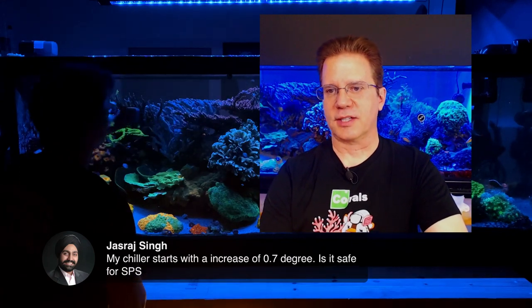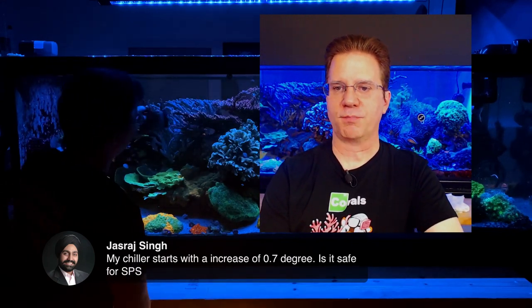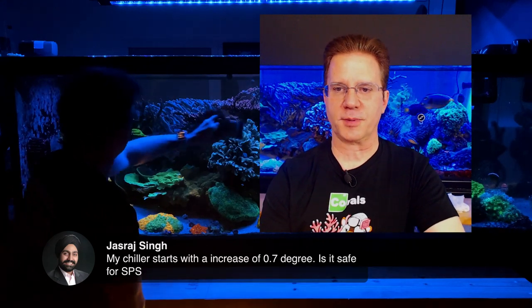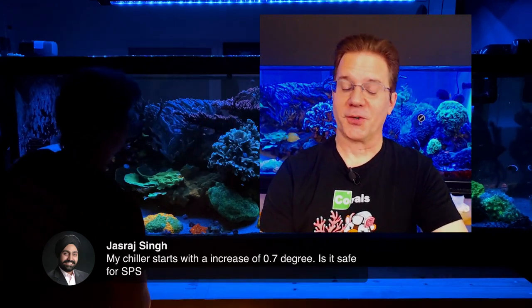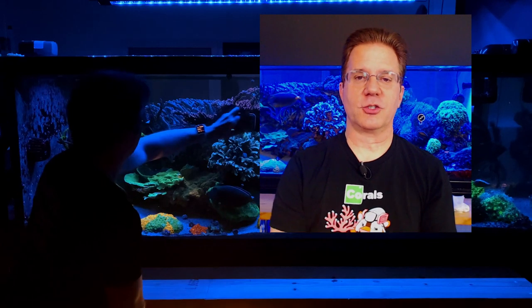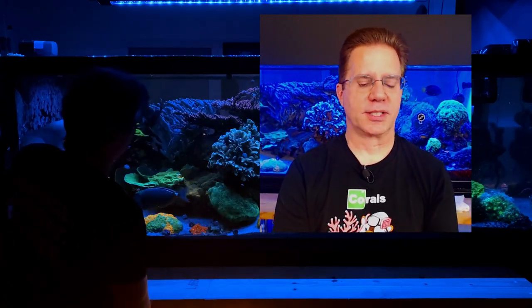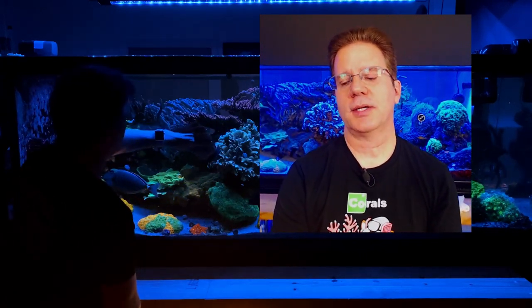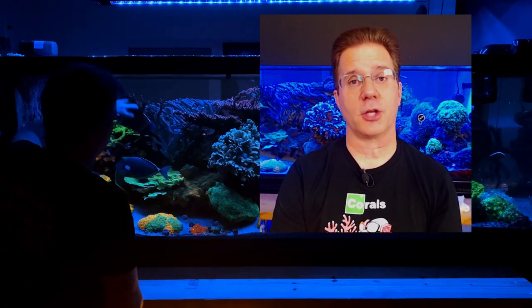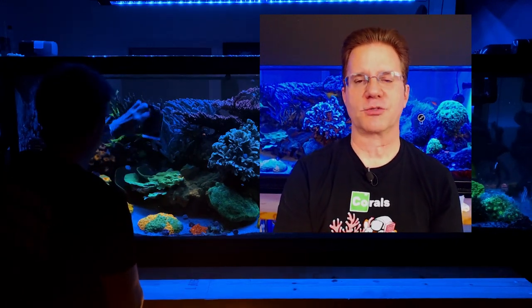Jess Raj says, my chiller starts with an increase of 0.7 degrees - is that safe for SPS? I don't know, I don't know what your area is. You just said when your chiller comes on, but that's a very tight margin and might be too tight. It might make your chiller cycle on and off a lot. It might be better to have like a 1 degree swing, 1.5 degree swing before the chiller comes on. But other than that, should be okay, assuming you're in the right range for the actual tank temperature.